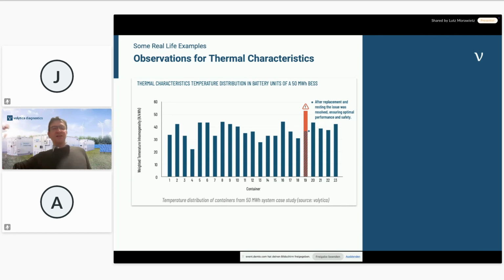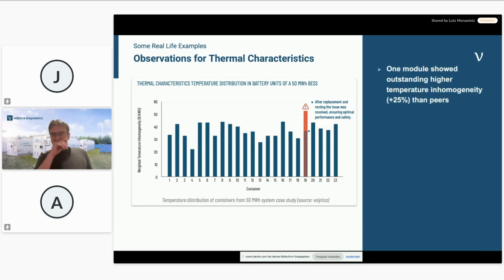In general, if the value is low, everything is fine. If it's high, it can be an indication that something's not okay. We detected one module, labeled orange, that stood out from its peers - it had more than 25% higher weighted temperature inhomogeneity than its peers. This is a peer group comparison we do here, so you won't find these values in any data sheet - it's simply expected that everything is well aligned.